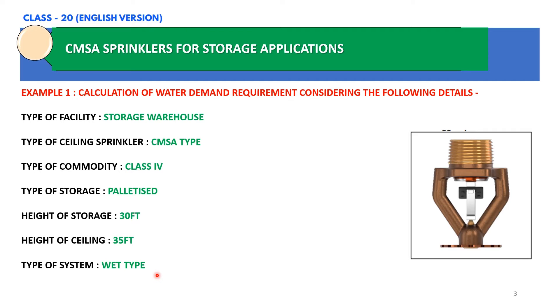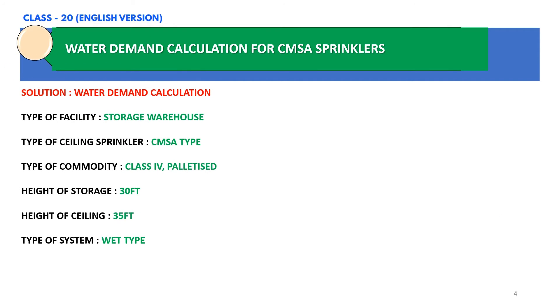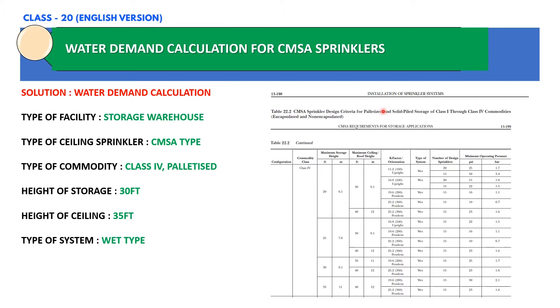All these details are provided and we need to calculate the water demand requirement for the CMSA type sprinklers based on NFPA 13. Based on the available data, we will refer to NFPA 13, the standard for installation of sprinkler systems. I have extracted table 22.2 of the 2019 edition of NFPA 13, which provides CMSA sprinkler design criteria for class 1 through class 4 commodities. From this table, we can find the K factor, the number of design sprinklers, and the minimum operating pressure for each sprinkler. The height of storage is 30 feet, ceiling height is 35 feet, system type is wet, and commodity type is class 4.